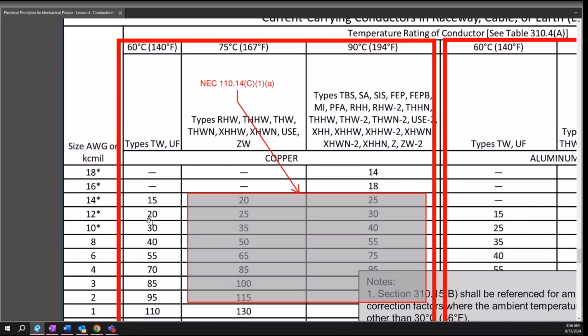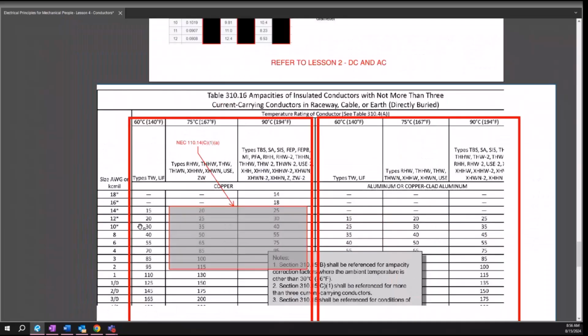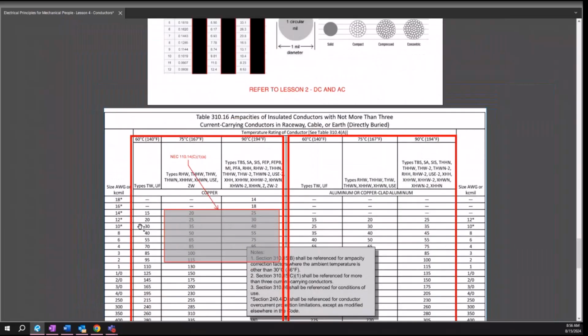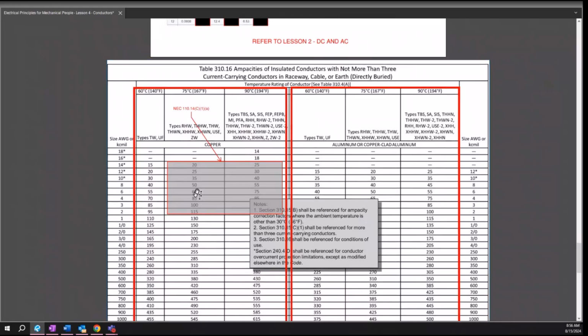There's also several derating factors if you're on the roof, or if you have more than 3 current carrying conductors, or if you're in an ambient temperature greater than 104, or less than like 60 C or something. I don't know. There's all sorts of additional numbers that you have to contend with, but I at least wanted to get this out there so that you could start getting your head wrapped around it, including the mark out here. And yes, the 2023 code still has requirements for a roof, because if you throw conductors right down on top of a roof, well, those are going to get stupid hot because a roof is hot, right? So you can't push as many amps down that thing.